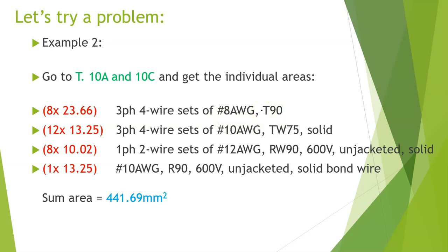Now you'll notice that this particular one does not say whether or not it's stranded or solid. However, if you go to tables 10A and 10C, what you will notice is that 10C, which is for solid conductors, only goes up to number 10 AWG. That's because they don't make it in solid conductor above that size. So they don't make number 8 solid. It would be simply too stiff to be used for any real effective installation. Hence, over the threshold of number 10, it's guaranteed to be stranded.